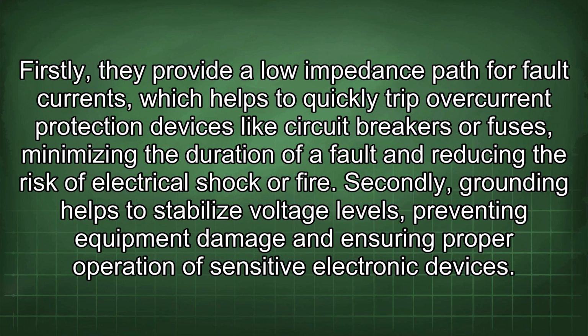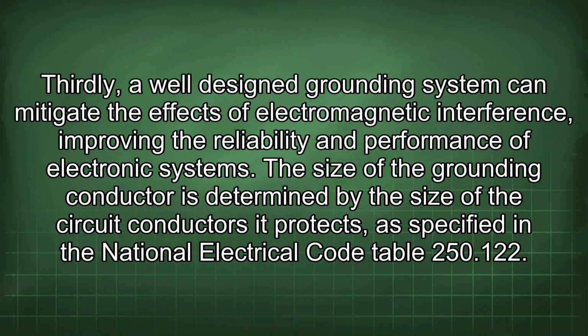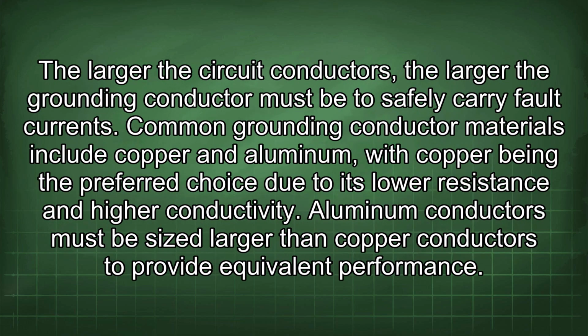Secondly, grounding helps to stabilize voltage levels, preventing equipment damage and ensuring proper operation of sensitive electronic devices. Thirdly, a well-designed grounding system can mitigate the effects of electromagnetic interference, improving the reliability and performance of electronic systems. The size of the grounding conductor is determined by the size of the circuit conductors it protects, as specified in the National Electrical Code Table 250.122. The larger the circuit conductors, the larger the grounding conductor must be to safely carry fault currents.